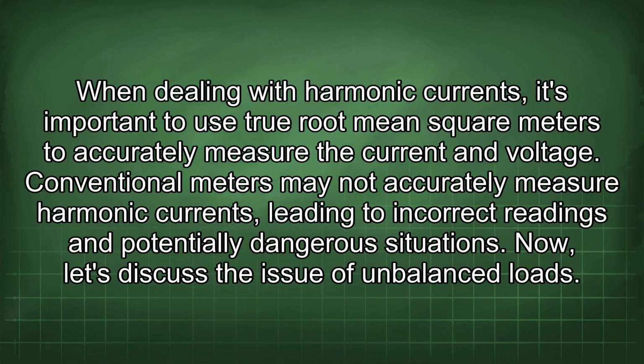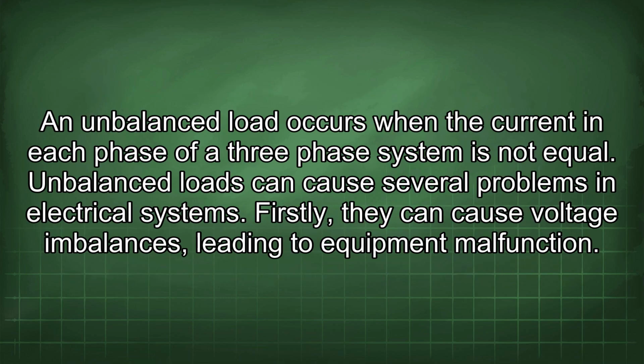When dealing with harmonic currents, it's important to use true root mean square meters to accurately measure the current and voltage. Conventional meters may not accurately measure harmonic currents, leading to incorrect readings and potentially dangerous situations. Now, let's discuss the issue of unbalanced loads. An unbalanced load occurs when the current in each phase of a three-phase system is not equal.